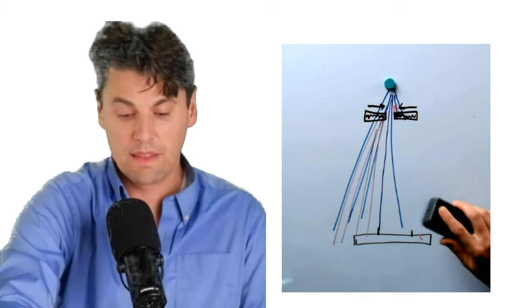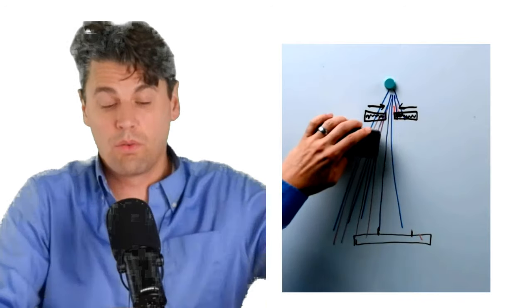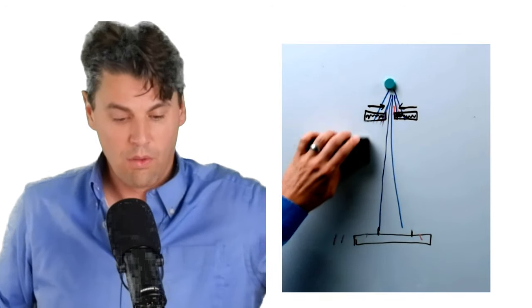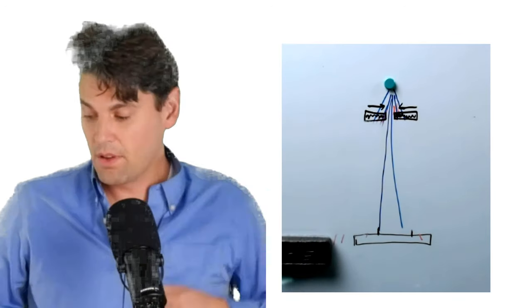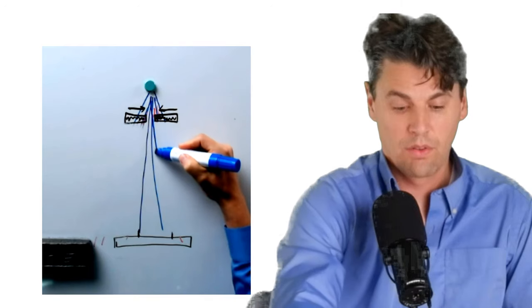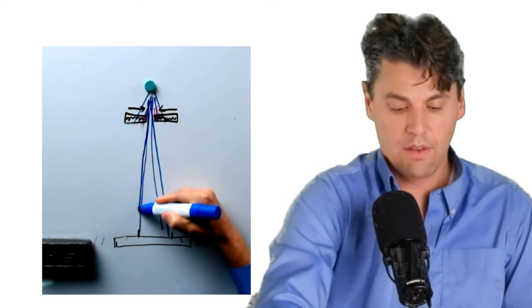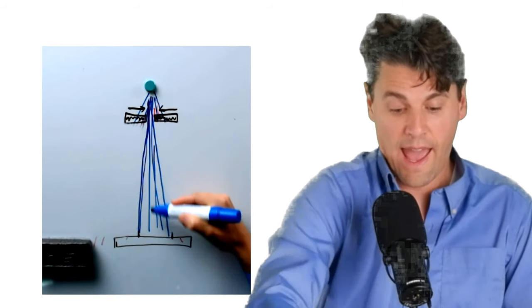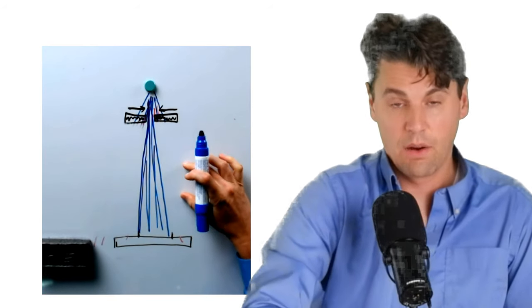The region of radiation which we would like to irradiate will have the primary radiation, and there will not be radiation out here in the region where we're blocking it primarily with these collimators. So the collimator is defined actually in a plane that's relatively close to the tube.